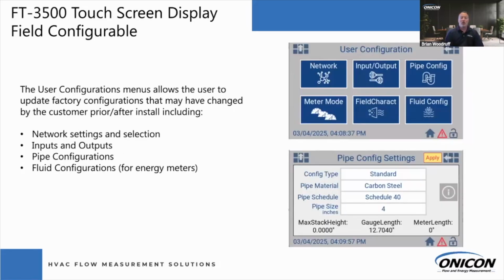Talking about configurable, we have the changes of the pipe. So for example, if you're in the field and you happen to order the flow meter for a 4-inch carbon steel pipe, schedule 40, and then you get out in the field and you see that it's a 6-inch, thankfully you won't have to contact ONICON. With the previous model, you had to actually fill out a form. You'd get an S19 file, which took 3 to 4 days. Then you'd have to get a laptop, be accessible to the flow meter, and download the information into the flow meter to make those changes. Thankfully, with the touchscreen display, you're able to quickly make those changes, and that doesn't affect calibration, which is great. So another great feature, like I said, we listen to our customers. We like to hear the issues they have in the field, especially from those contractors or the utility managers that are using these meters.